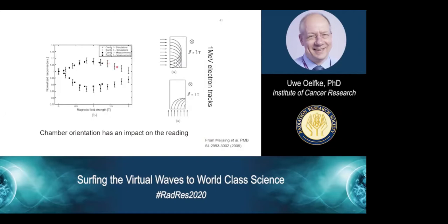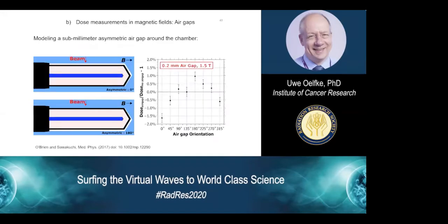But of course, if the field strength gets too high, then these electrons are leaving fast, and therefore you get this pattern. If you have the other orientation of the cylinder, in parallel direction, you see that the electron tracks which are created have a shorter way before they leave the ionization chamber, and therefore you have this characteristic signal. And again, the higher the field strength is, the smaller the path length of the electrons in the chamber. But these effects are understood and can just be accounted for by consistent and well-regulated measurement protocols.